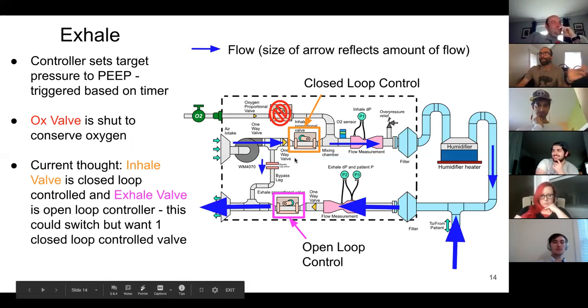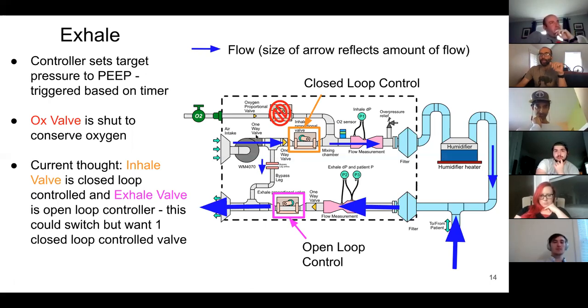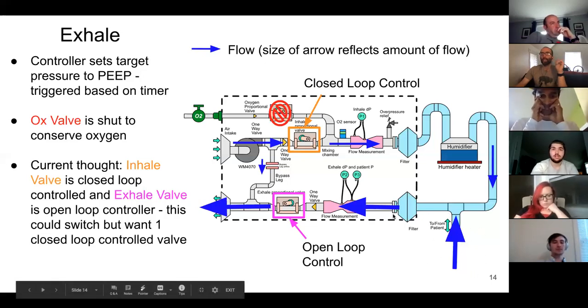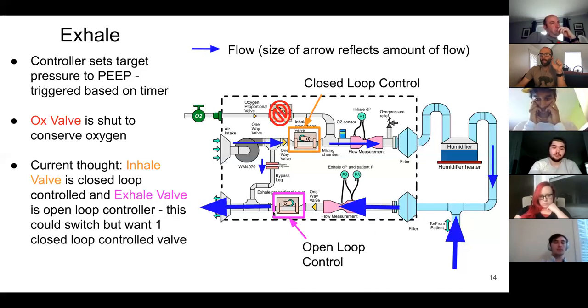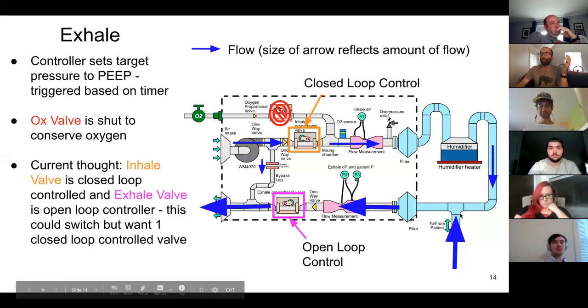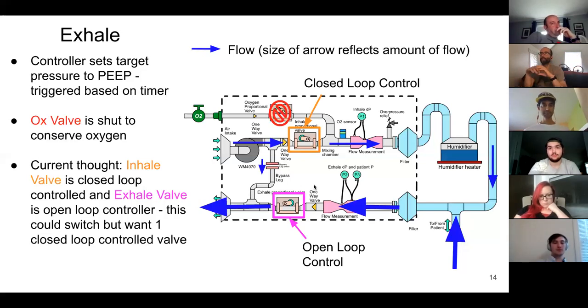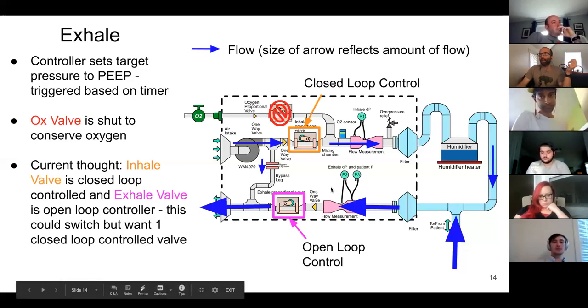But what happens during exhale is we close the oxygen valve to keep the flow loss down. The fan is open loop control. It's still just running, and maybe we turn it down slightly, but we modulate the pressure. So we need to establish PEEP during exhale. To establish PEEP while the patient exhale rate is changing, we're building resistance against this valve. So all the flow is going out and dropping pressure as it runs against this restriction. The amount of flow is proportional to the pressure drop, and the pressure drop is what's seen by the patient. So if we're trying to maintain a PEEP of 20 centimeters, we need enough flow going through this partially open valve to establish that PEEP. That's something that we'll have to talk through between the controller and the physical implementation and how that actually gets put in place. But that's sort of the theory, that we're going to let it leak and just push more flow through it.